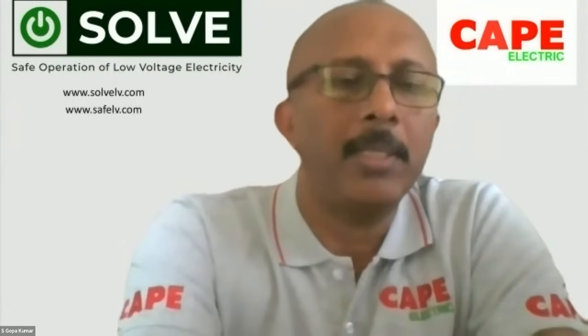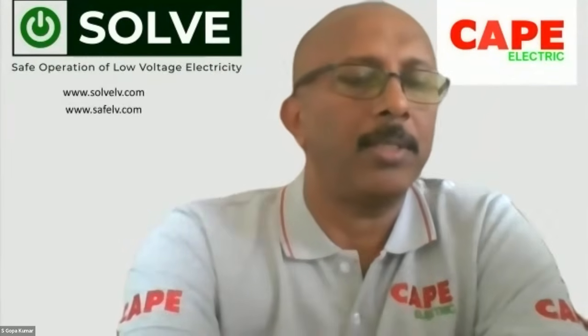Pramod Dwivedi is asking, kindly confirm temperature measurement on both places, like terminal points and body of the power contactor. Some people say only temperature measurement at the terminal point is okay. No, the first point of measurement is the continuity resistance. If there is a loose contact, of course, high temperature can be created once the conductor carries current. So the first test to be carried out is the continuity resistance test.